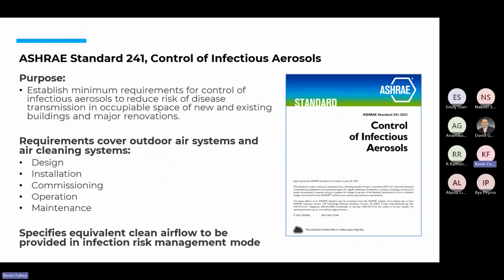So the purpose, again, is to minimize the risk of disease being transmitted within an occupied space. And this does a little bit more than prescriptive. It is prescriptive in the design, but it also talks about the installation. It talks about commissioning it, and operating and ongoing maintenance. And all these details are in a 48-page standard that you can buy at the ASHRAE bookstore.